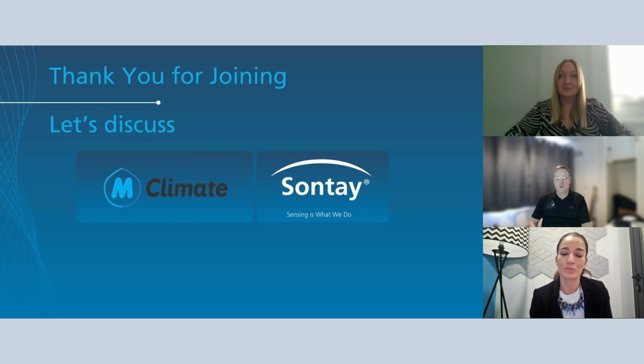I walked out of the plant room to the estates office, which was at least half a kilometre away. I got there and was able to demonstrate to the BMS manager, using a field test device, that we were still sending and receiving signals to the gateway, even though it was locked away in a plant room in the middle of a building. He was immediately sold on it, as you can well imagine, and all of a sudden the possibilities opened up for him. Now that's no guarantee that in every plant room, inside every control panel, we'd be able to do that, but I'd say that was as close to a worst case scenario as I've ever seen for a wireless solution, and LoRaWAN came out with 5 stars.